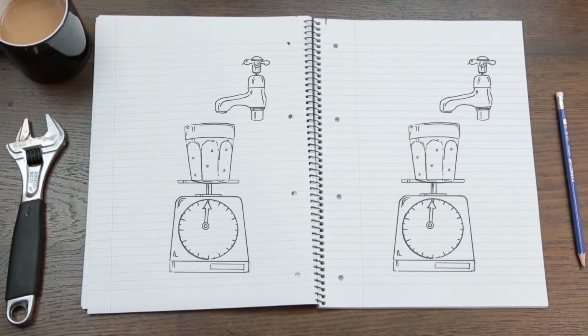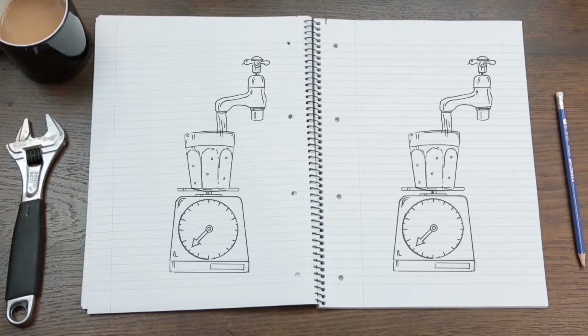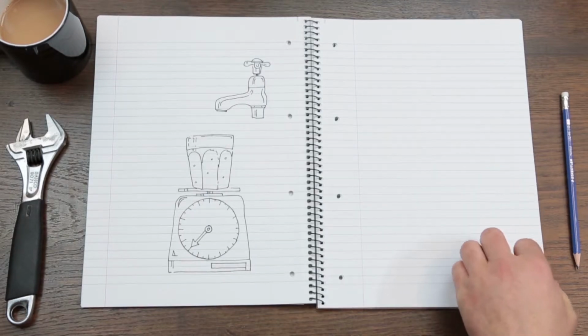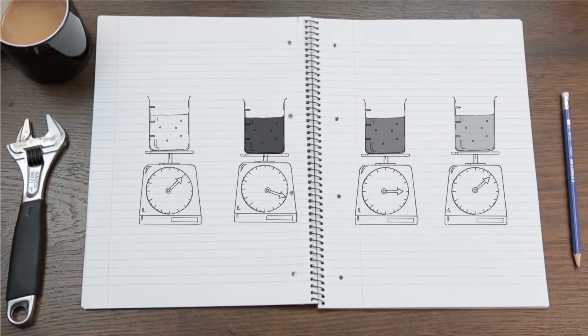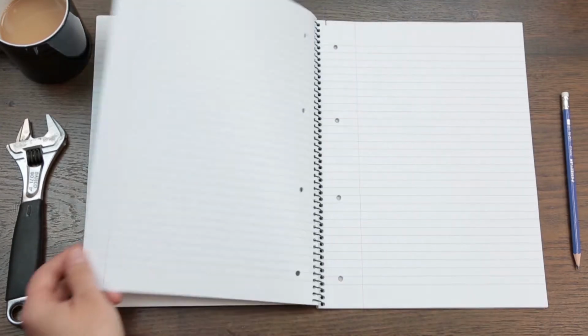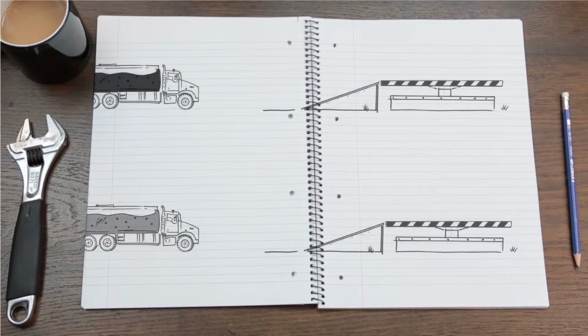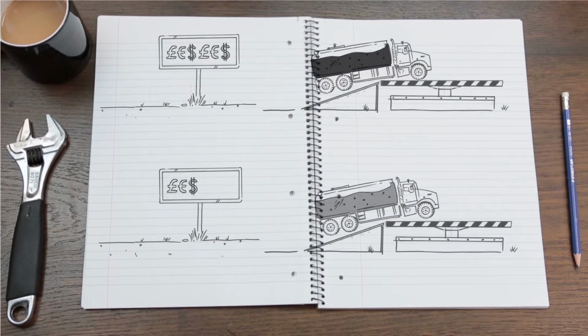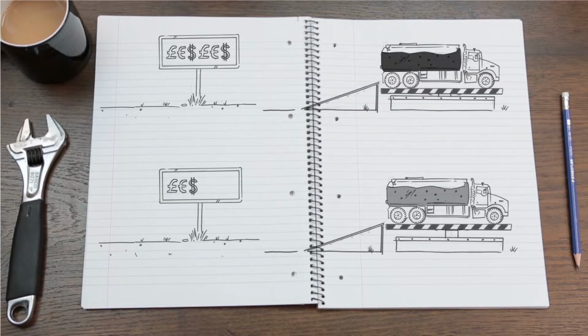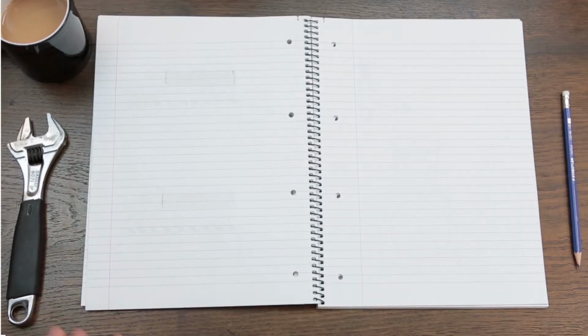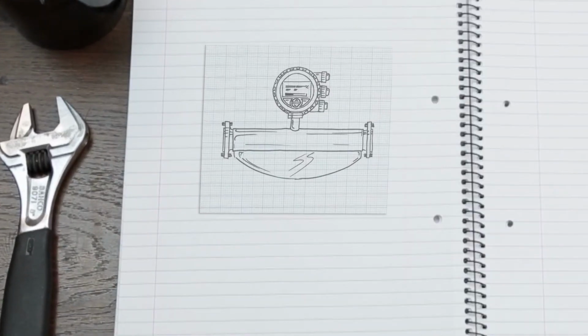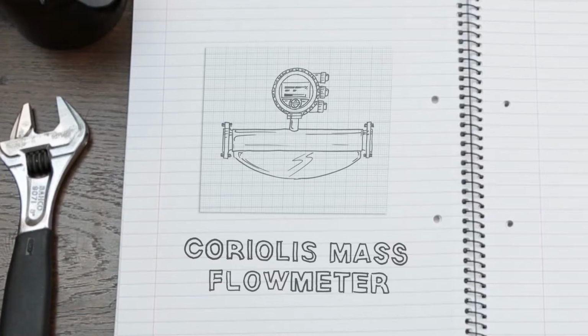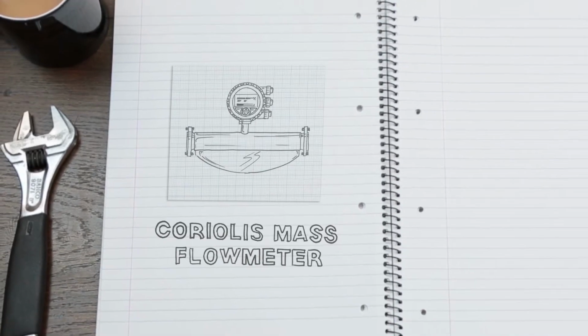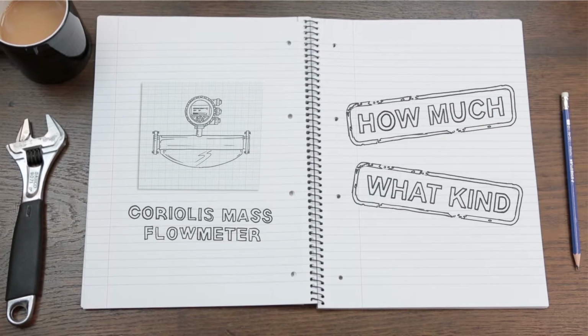With a liquid like water, you can accurately assess mass by measuring volume, because the density is known and doesn't vary much. Many high viscosity liquids are sold by mass, which is often mistakenly called weight, but that's another story. Different grades of oil have different densities. By measuring the mass of a quantity of oil as it is dispensed and dividing it by the volume, you can immediately verify the density and therefore the grade of oil you have bought. For that, you need to know the mass, and a mass flow meter will tell you this. So in short, mass flow can tell you the quantitative and qualitative information about a liquid that volume flow cannot tell you.